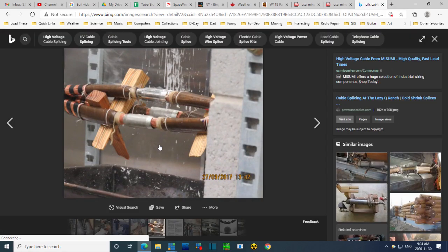So here's a three-phase cable. This is exactly what I was working with. Paper insulation here. See the paper's brown? It's called kraft paper. Kraft paper is paper that has not been processed all the way. It has not been bleached white because nobody cares. But if you bleach this stuff white, you can't get the bleach molecules, whatever that is, out of the paper enough to build a cable, because you can't have anything conductive in here. This is very, very special paper, which maybe I'll say a little more about in a minute.